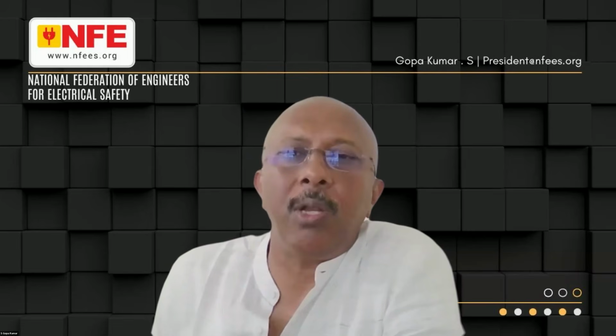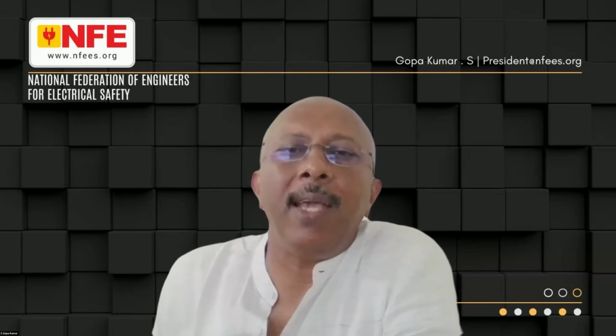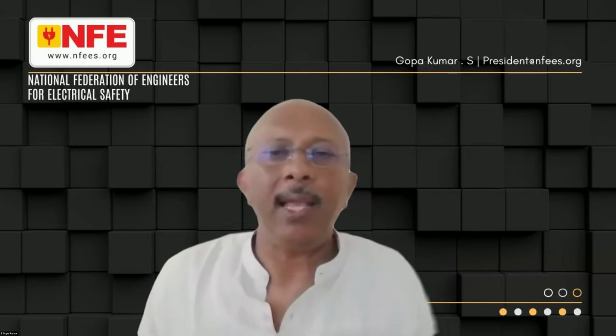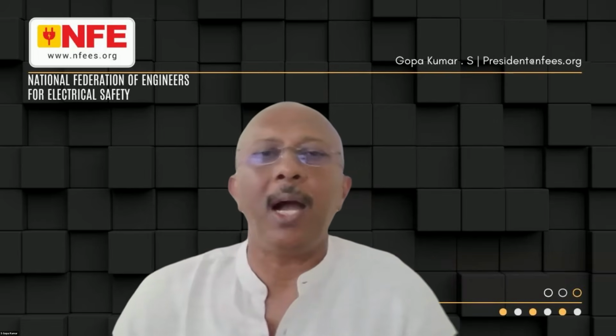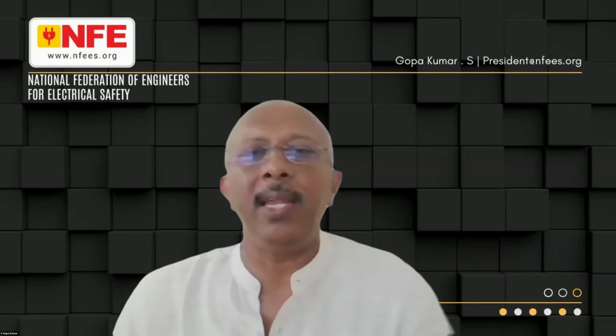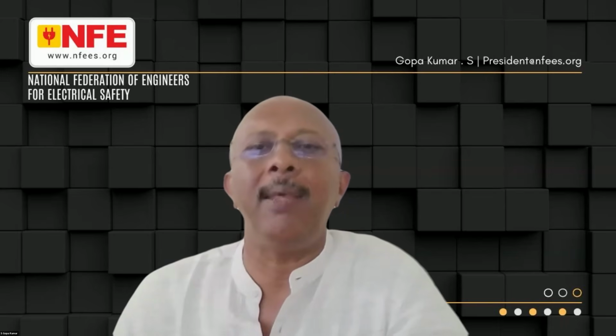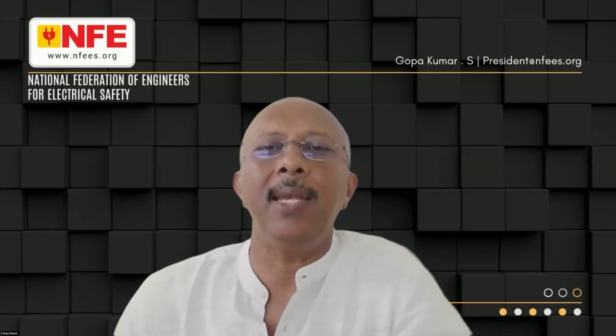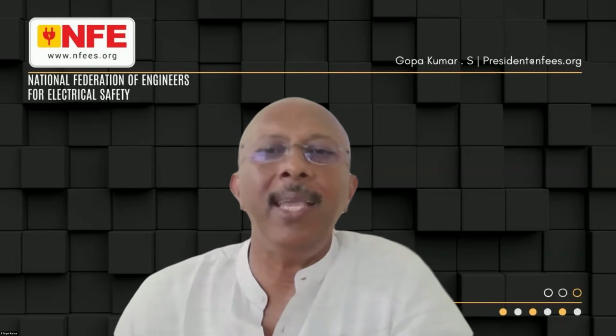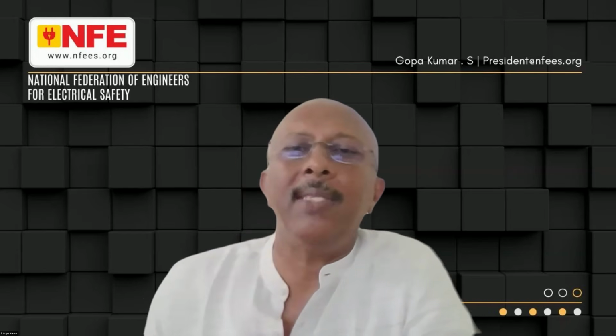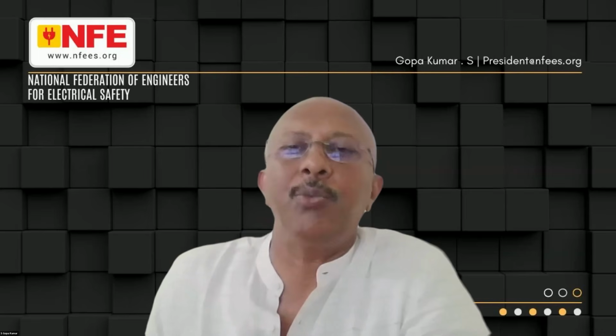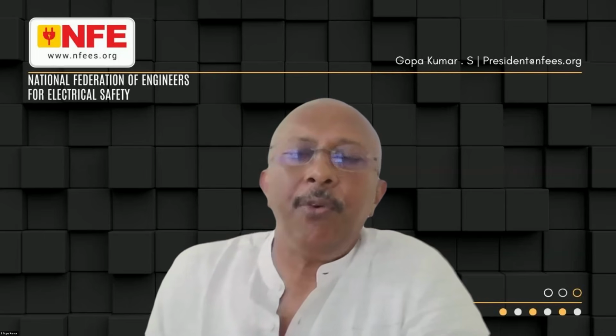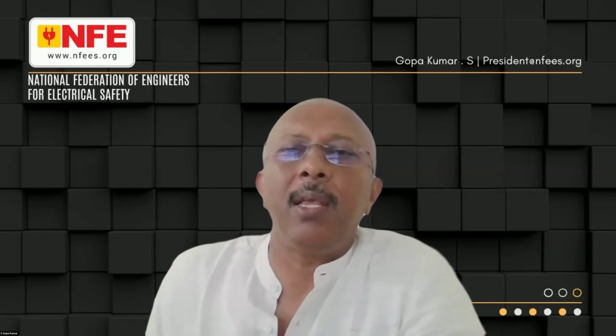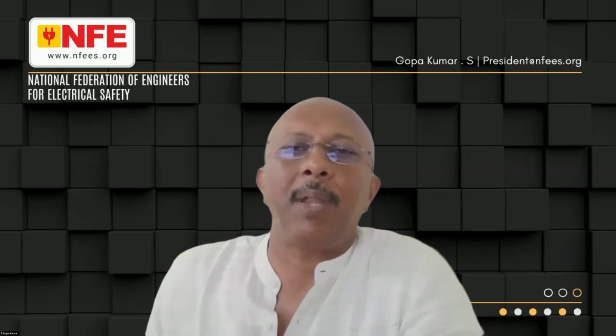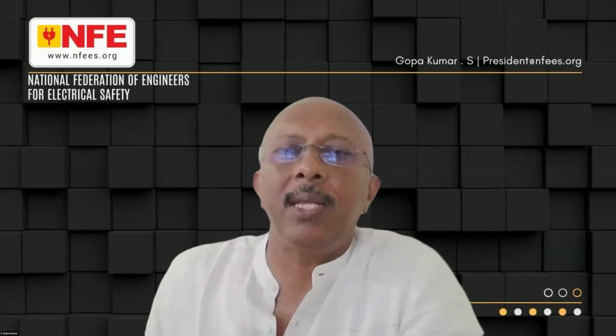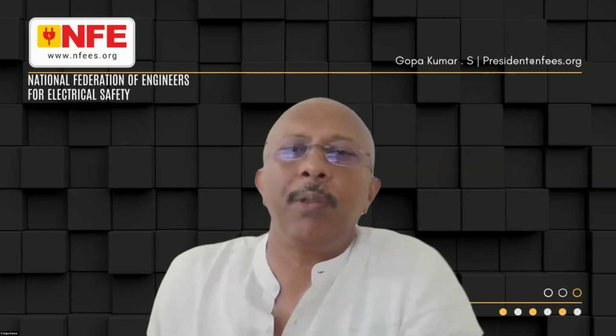I'm sure all of you are aware of the fire triangle. The fire triangle is a scientific way of explaining how fire takes place. It needs oxygen, it needs fuel, it needs temperature. Electricity is creating temperature, or heat, and the heat is because of the short circuit. So before conductive parts become hot, you must disconnect the supply. It is not the short circuit, it is the disconnection which is much more important.